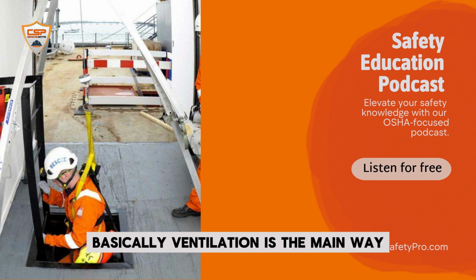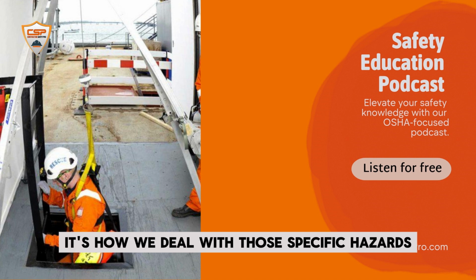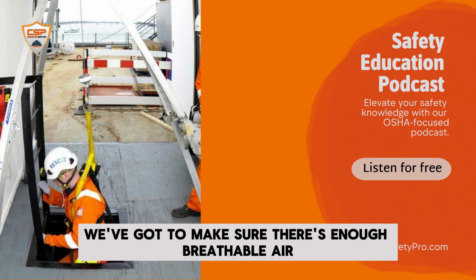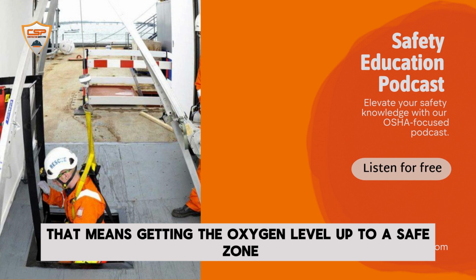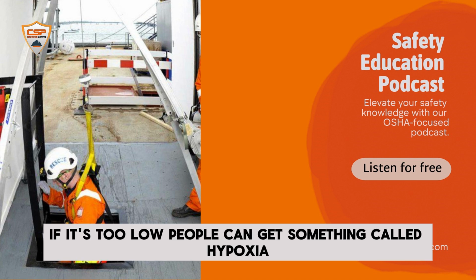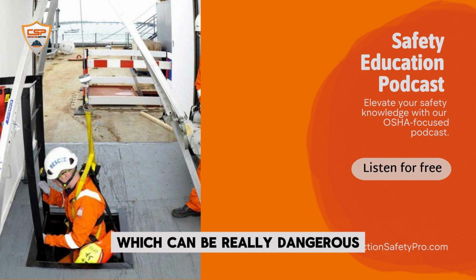Basically, ventilation is the main way we make a confined space safe to enter. It's how we deal with those specific hazards we found in the risk assessment. And there are three big goals here. First, we've got to make sure there's enough breathable air. That means getting the oxygen level up to a safe zone, which is usually between 19.5% and 23.5%. If it's too low, people can get something called hypoxia, which can be really dangerous, even deadly.